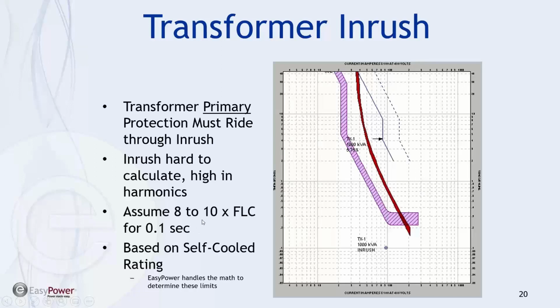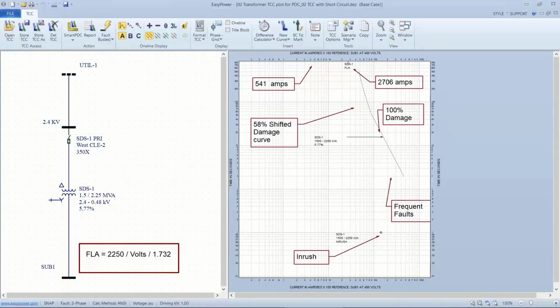So what I'd like to do is to jump into EasyPower and show how these controls are adjusted and make sure that you're aware of your ability to control these. So first of all, this is the plot for this particular transformer. It's a 1.5 MVA transformer with a 2.4 kilovolt primary and a 480 secondary. And the tool will calculate the full load current, in this case, on a 480 volt reference.